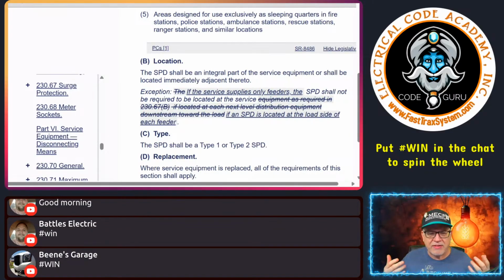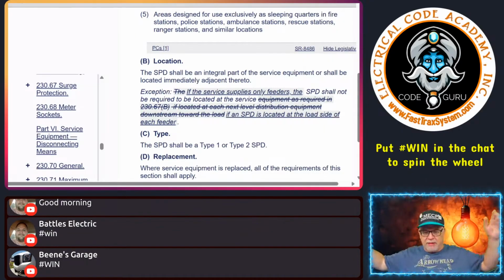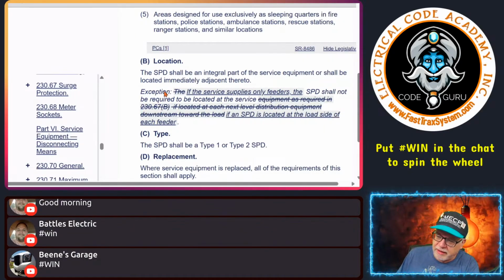Immediately adjacent is right there. A lot of people say within arm's width, whatever. Now here's the exception: if the service supplies only feeders, the SPD shall not be required to be located at the service if an SPD is located at the load side of each feeder. So this is an allowance saying it doesn't have to be at the service if it can be at each feeder.